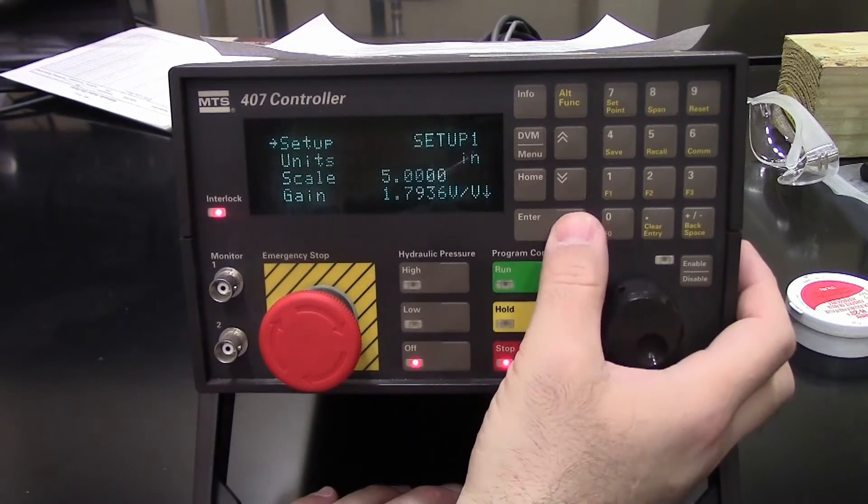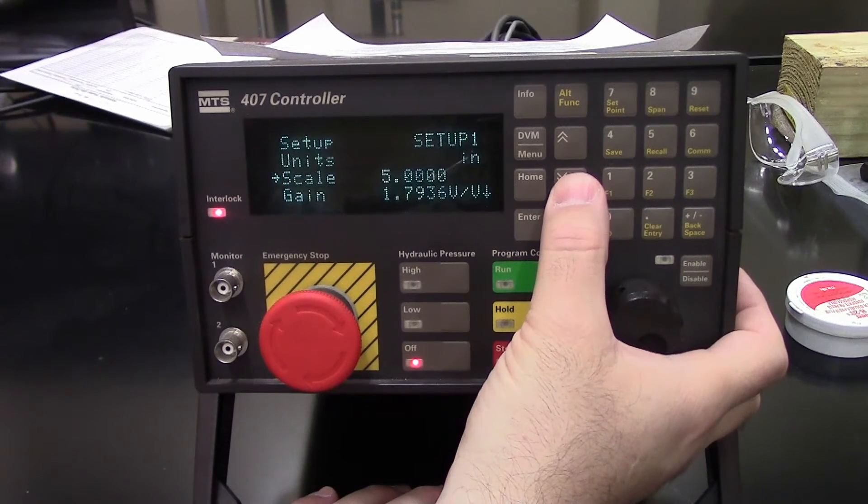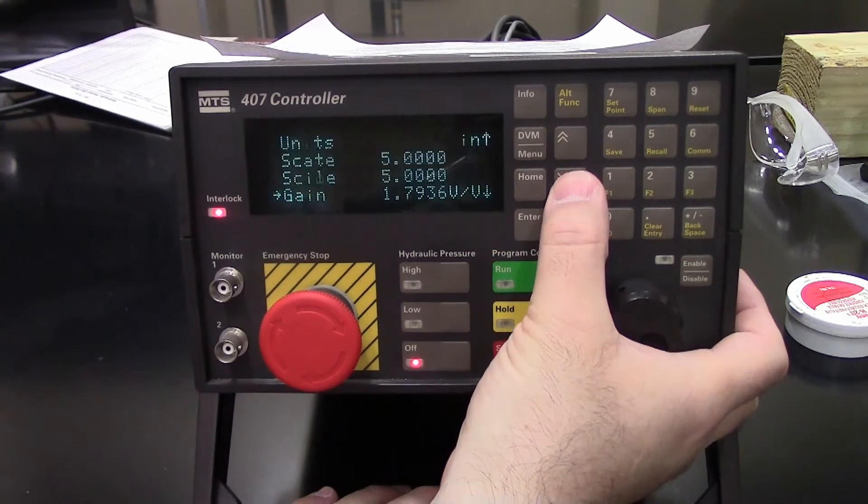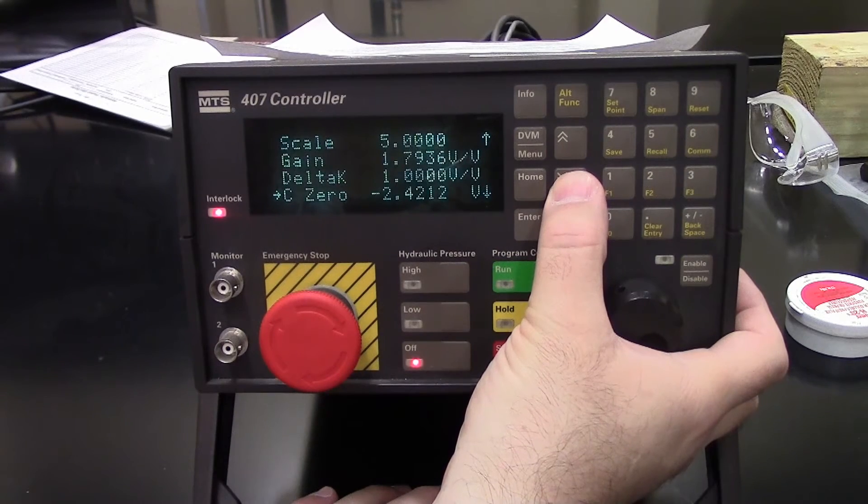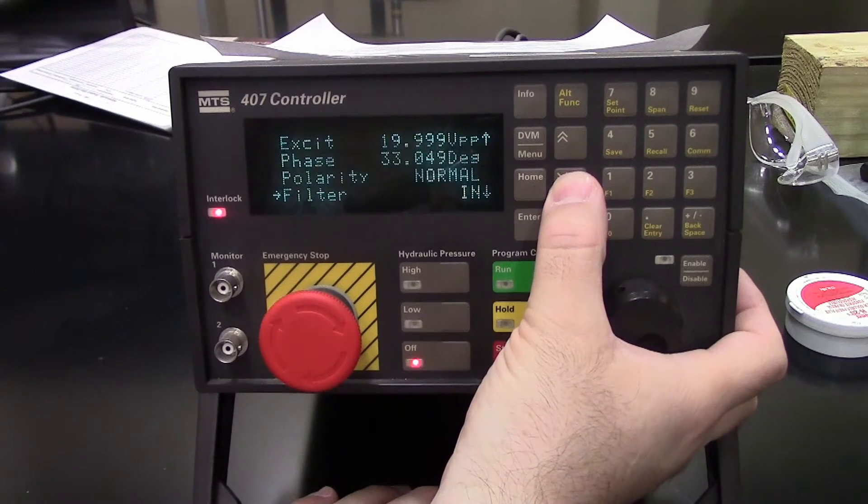AC1 conditioner. This is in setup 1. It has our units. Five inch full scale. It has the gain, the delta K, and the coarse zero. This would depend on your calibrations. Here's the excitation and phase and polarity.